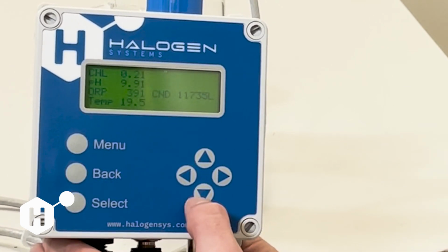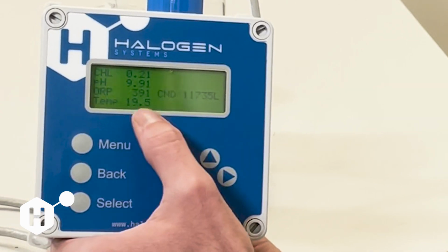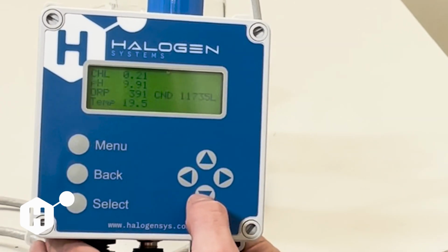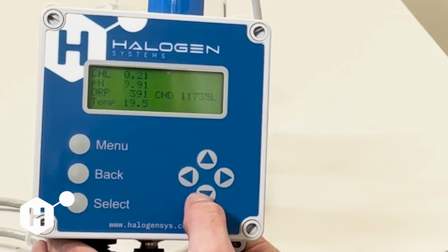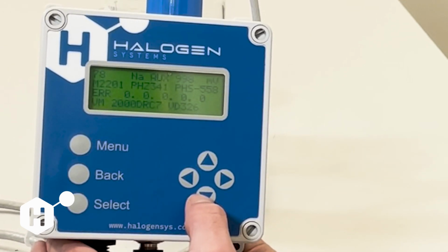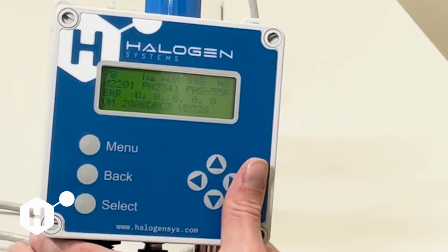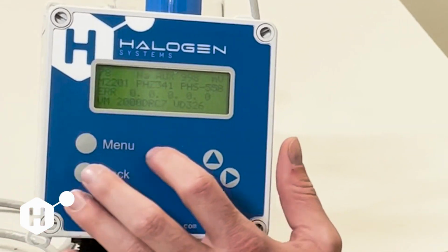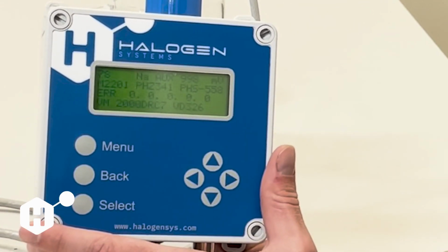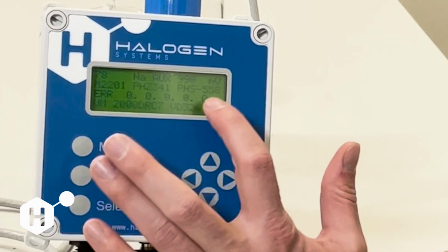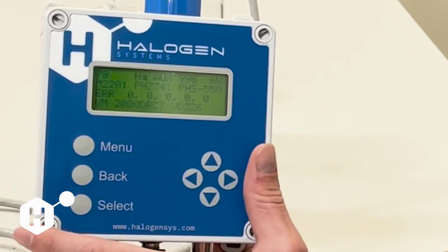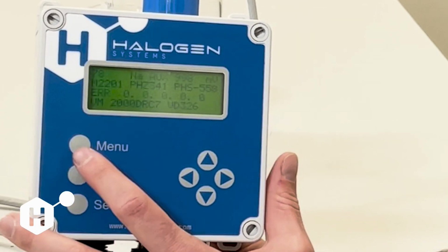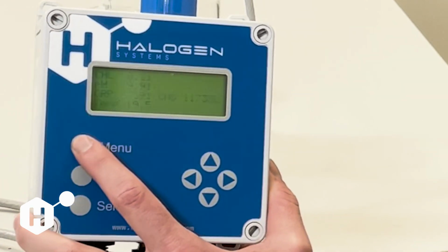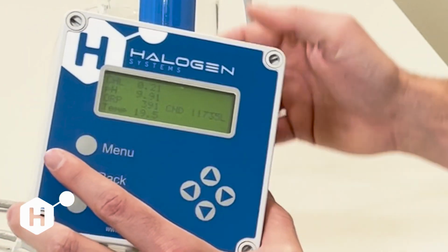So we're at 9.91. I'm feeling better about that calibration. We're pretty close. We are not at 25C, so I am expecting a little bit of a pH difference here. And we look over here, 55.8, which tells us that our calibration has updated. You'll notice that there is no decimal place there. We ran out of space on that screen, so there is a single decimal place, even if it shows a couple digits. So we can go back to menu and take a look, and we're looking pretty good.